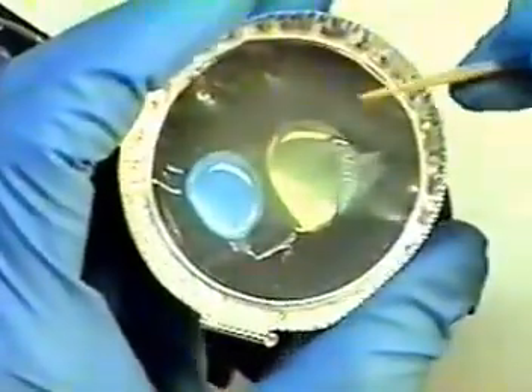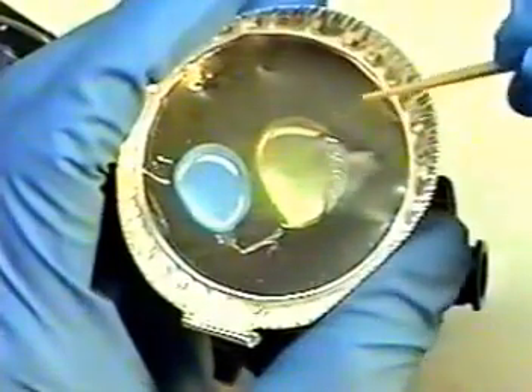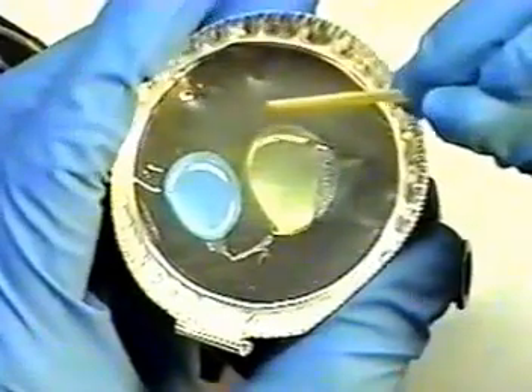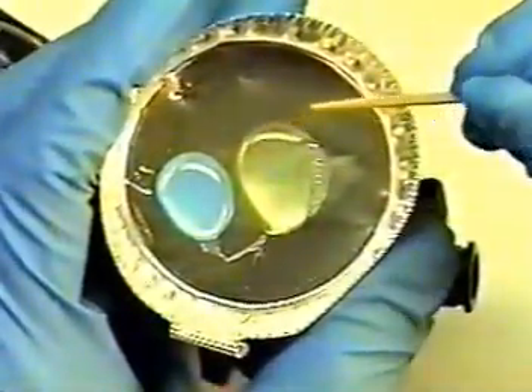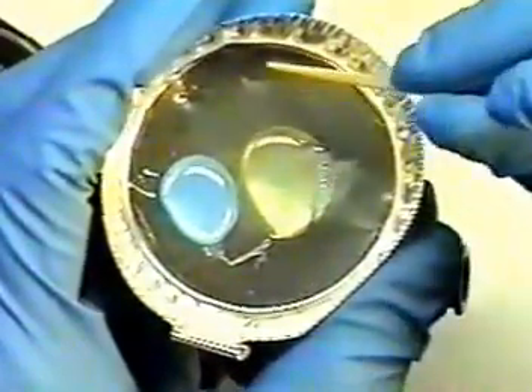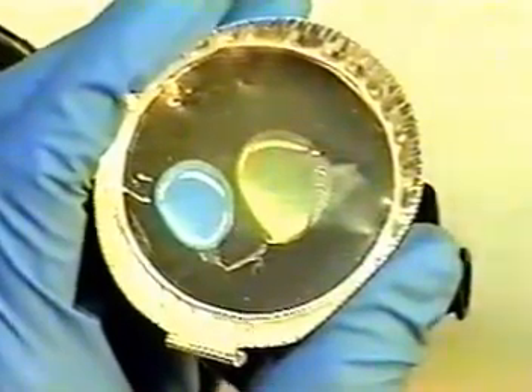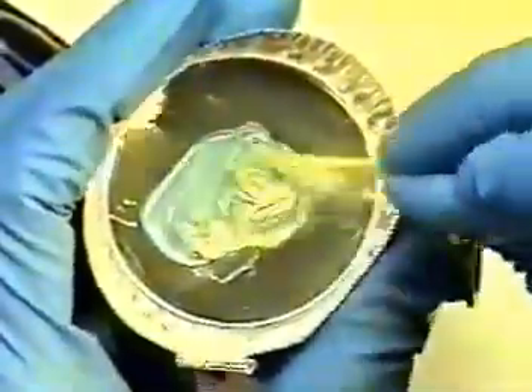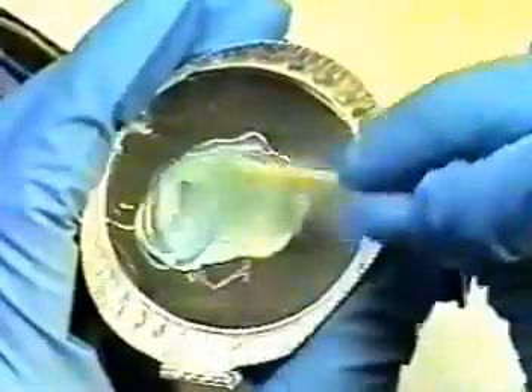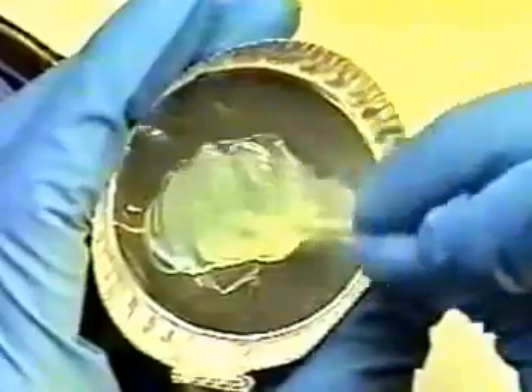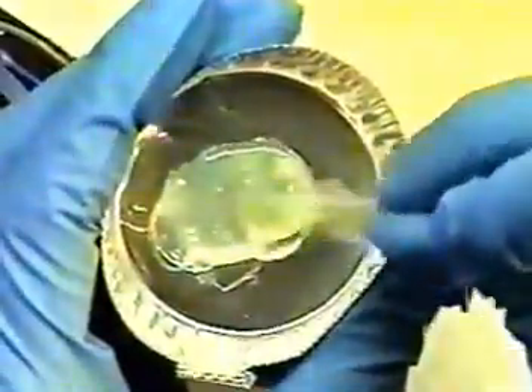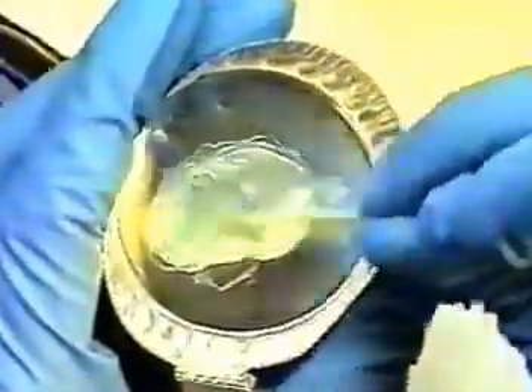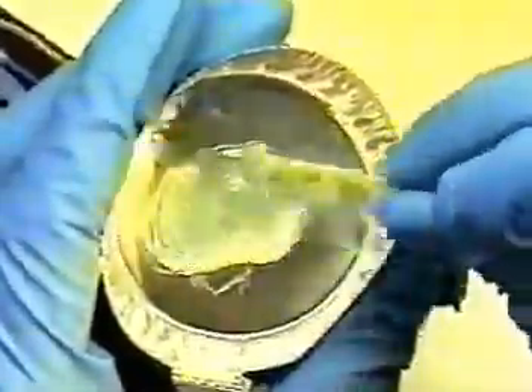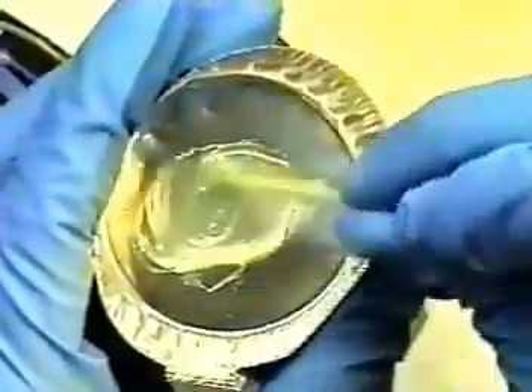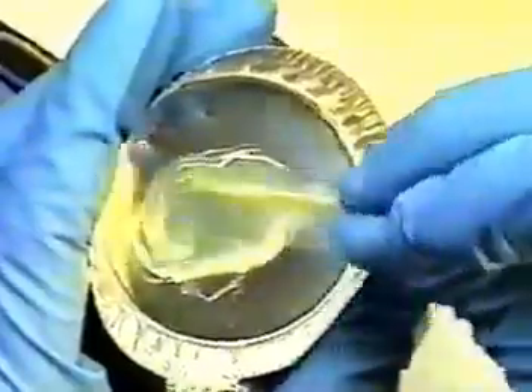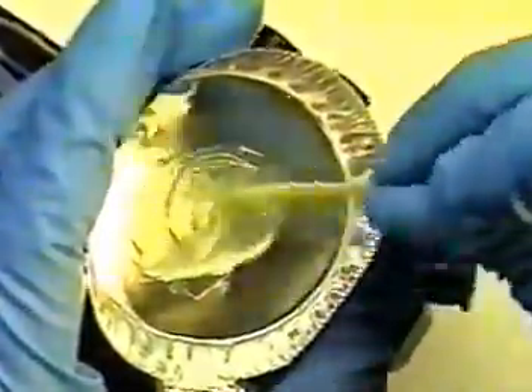We will now need to mix some epoxy to glue our suction channel onto the suction channel port. You could use either a 5-minute Class 6 epoxy or a standard 2-part epoxy. Part number is SPBRE or SPBRE5. Mix your epoxy previous to gluing. If using the 5-minute, you will need to perform suction channel placement quickly. If using standard bending rubber epoxy, you'll need to leave it sitting at least approximately 1 hour till it gets tacky, otherwise it will run down inside the body of the endoscope.